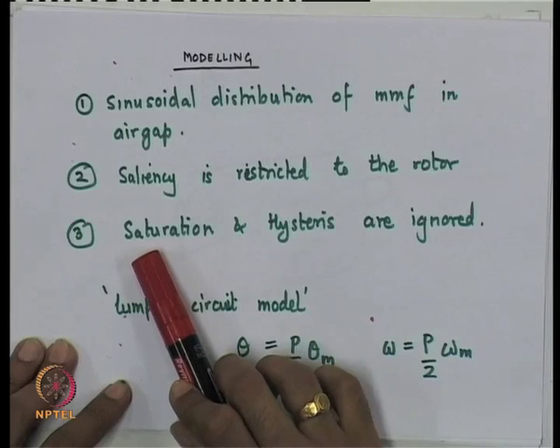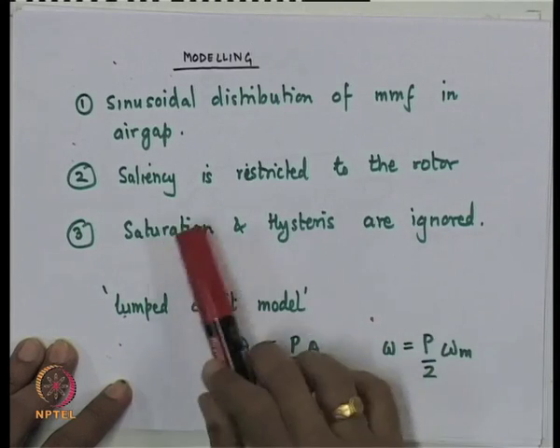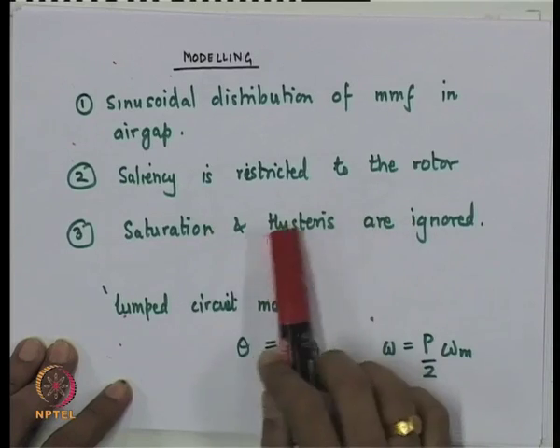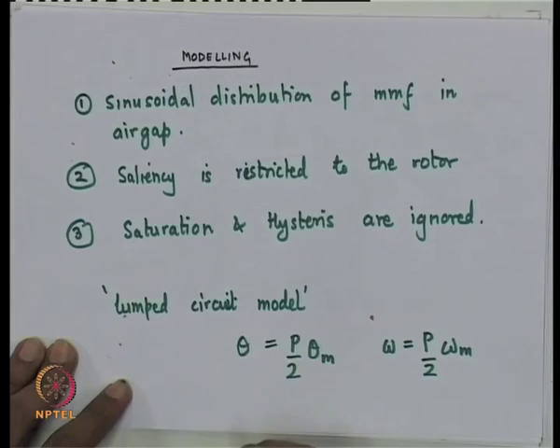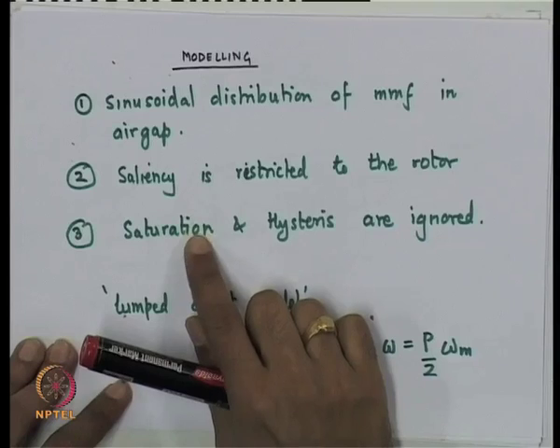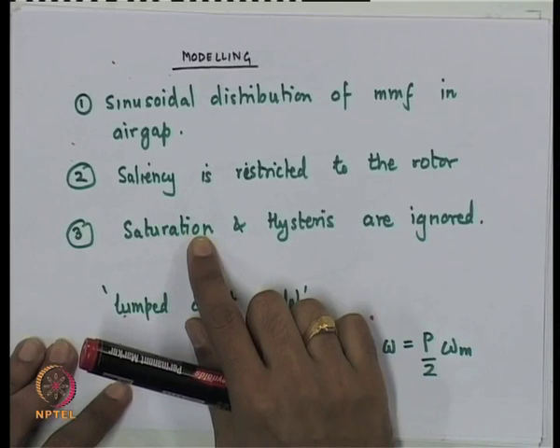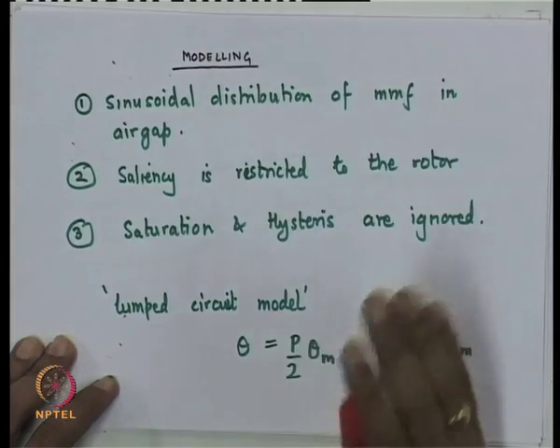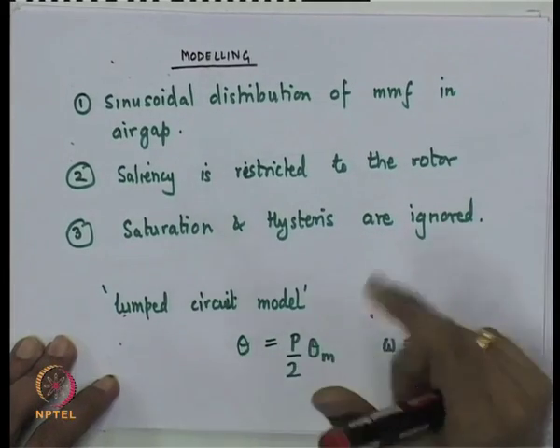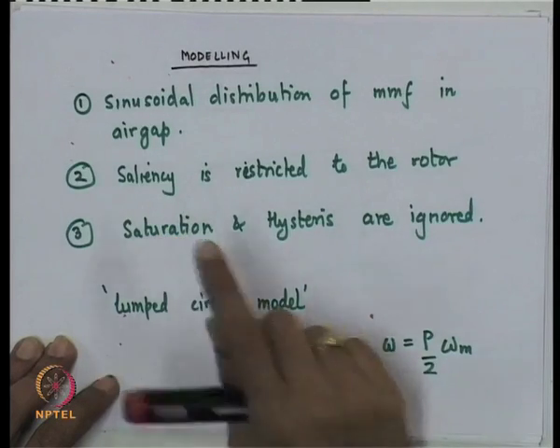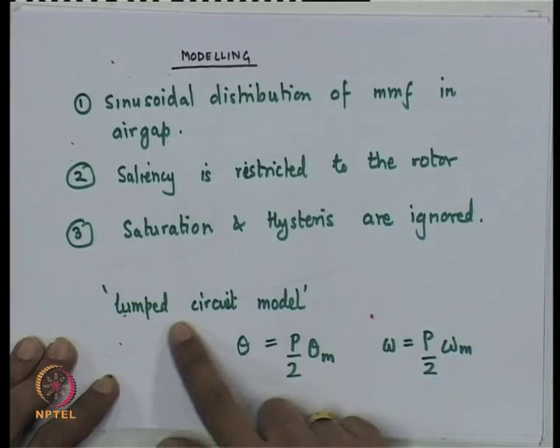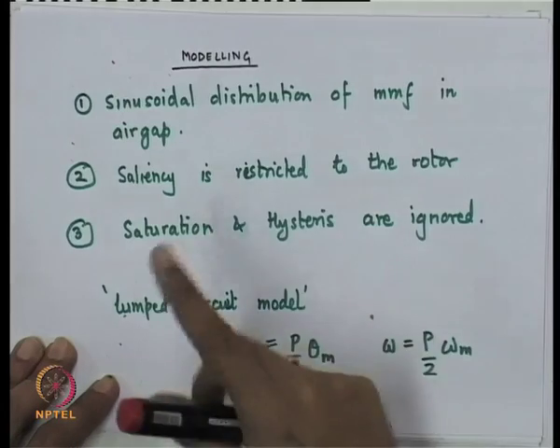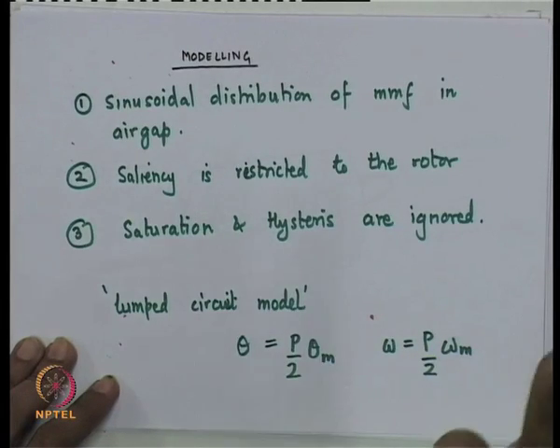Another very important assumption is that saturation and hysteresis are neglected, so we treat the machine as a linear magnetic circuit. This simplifies analysis greatly. At some point we may need to relax the saturation assumption for realistic answers, and we will add corrections for saturation to the basic model. Our lumped circuit model will not include parasitic capacitances or winding capacitances, so it is effectively restricted to relatively slow transients.